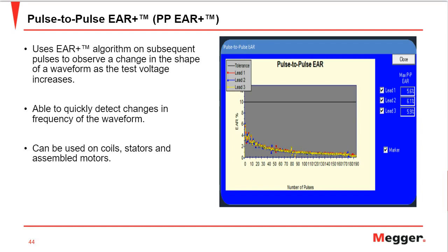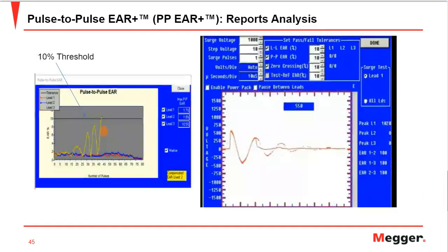We'll see a few examples of the pulse to pulse EAR. Here are two examples which clearly failed the pulse to pulse EAR. Two exactly identical waveforms will have an EAR of 0.0%, so there would be no difference between those two waveforms. Two waveforms that look identical to our eyes can have a difference of 4 to 5%, but that's still under the accepted values. We would notice non-identical waveforms if the difference is 10% or higher.